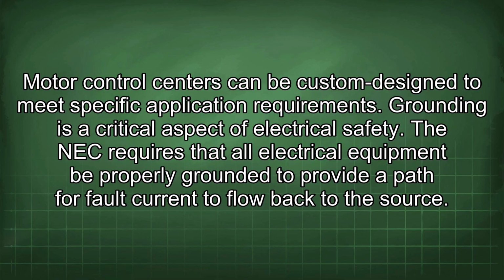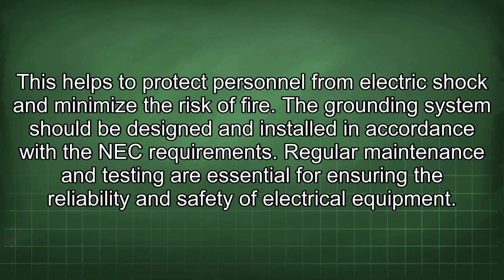Grounding is a critical aspect of electrical safety. The NEC requires that all electrical equipment be properly grounded to provide a path for fault current to flow back to the source. This helps to protect personnel from electric shock and minimize the risk of fire. The grounding system should be designed and installed in accordance with the NEC requirements.